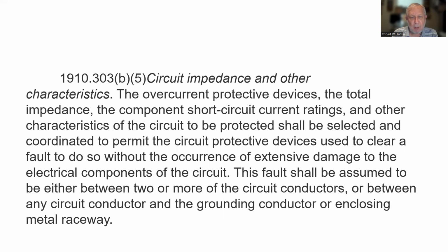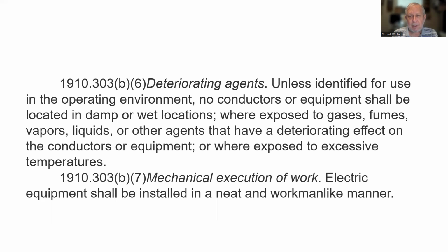Circuit impedance and other characteristics. The overcurrent protective devices, the total impedance, the component short circuit current ratings, and other characteristics of the circuit to be protected shall be selected and coordinated to permit the circuit protective devices used to clear a fault to do so without the occurrence of extensive damage to the electrical components of the circuit. This fault shall be assumed to be either between two or more of the circuit conductors or between any circuit conductor and the grounding conductor or enclosing metal raceway. Deteriorating agents. Unless identified for use in the operating environment, no conductors or equipment shall be located in damp or wet locations or where exposed to gases, fumes, vapors, liquids, or other agents that have a deteriorating effect on the conductors or equipment, or where exposed to excessive temperatures.